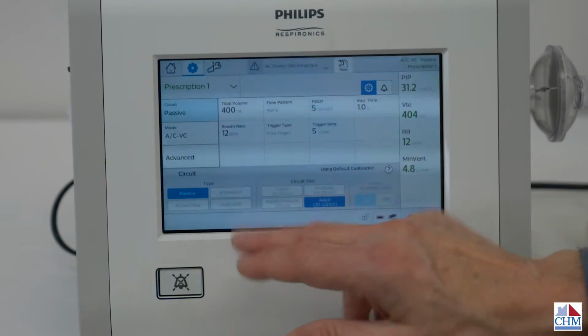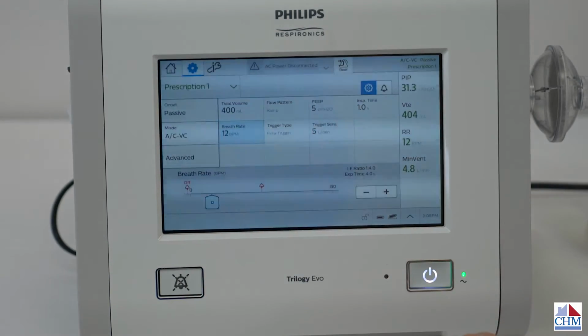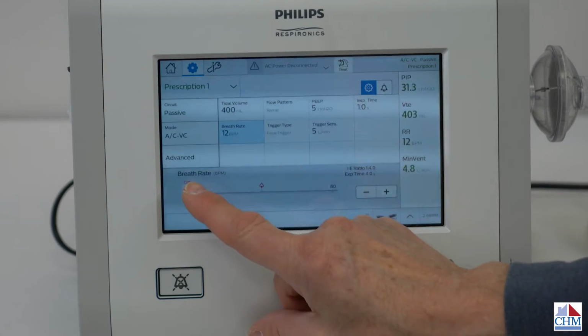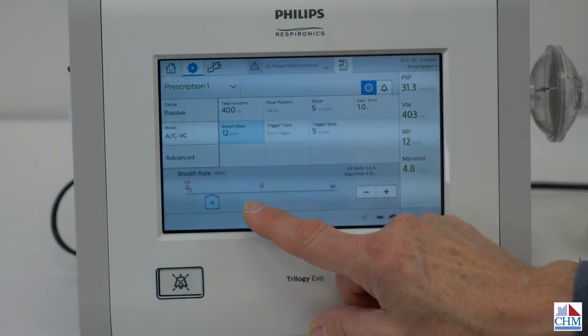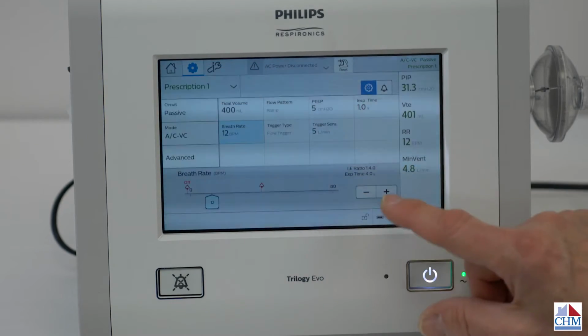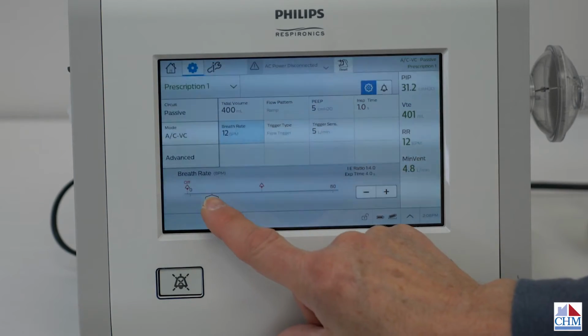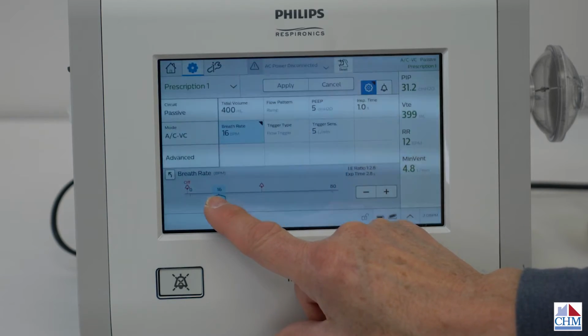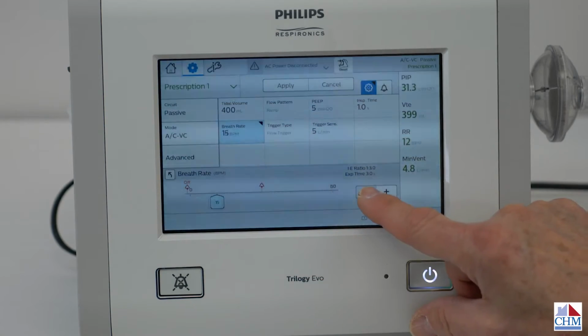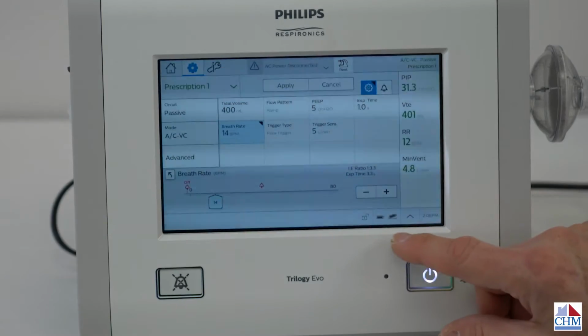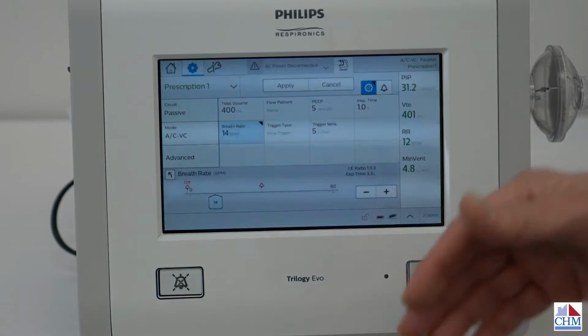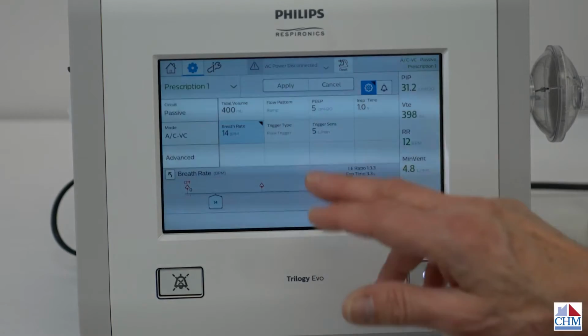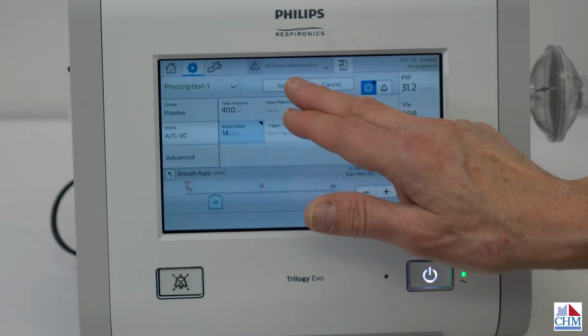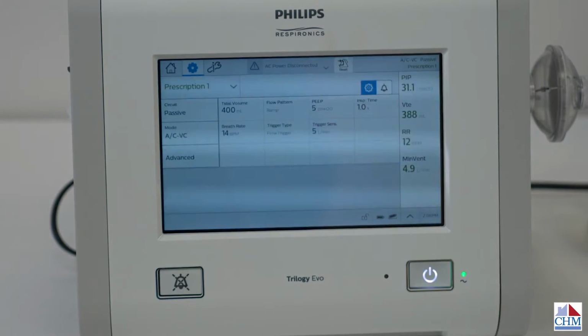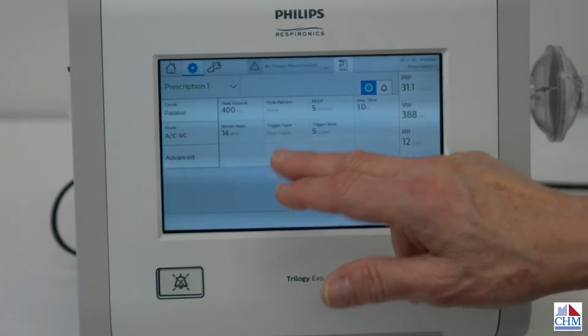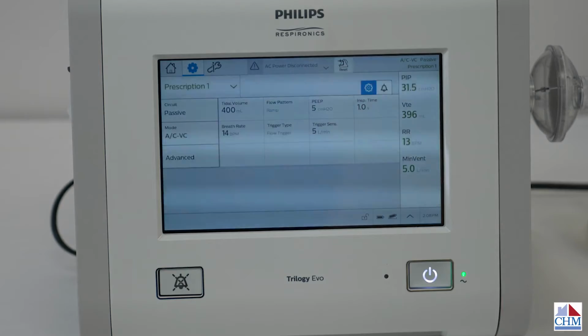If we wanted to change that, we could just tap the breath rate. And if you notice down here, it says breath rate, and it gives us a sliding scale right here, and then a plus and minus. You can actually grab the icon there and move it, or you can just use the minus and plus buttons over here in order to change that. Any changes that are made are not accepted until you hit the apply button. So hit the apply button and you're all set. And that locks that in, so now we're at the rate of 14.